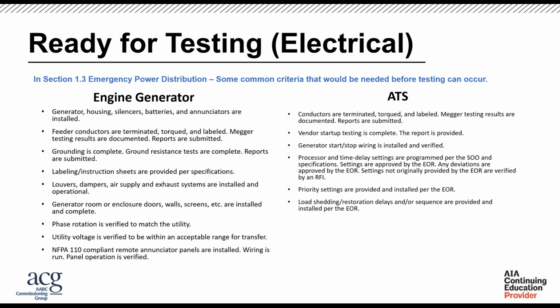I've run tests where, unfortunately, the HVAC system and the exhaust system might not have been ready. So they wanted to test with the doors open to make sure you didn't overheat the generator. However, this is not in that final condition. And then we had to come back when the HVAC system was ready. So in order to reduce wasted trips, and because on some projects you might not have the luxury of being able to come back, you don't have that 100% accuracy that when you're in an emergency the generator's going to work perfectly. You also want to make sure your fuel oil, if you have a large system where you're going from tank to tank and moving the fuel oil around, is working, or that you just don't overheat when it's in an enclosed space.